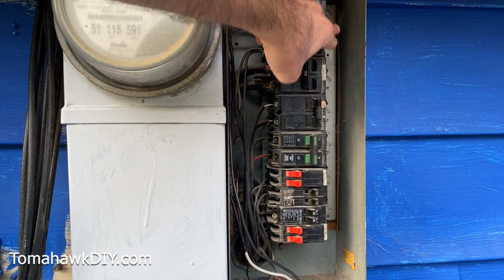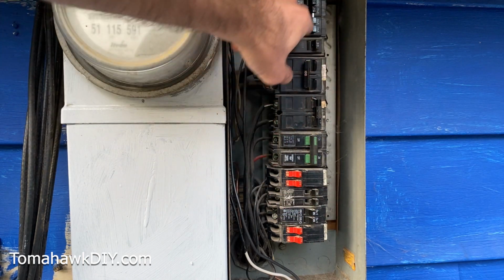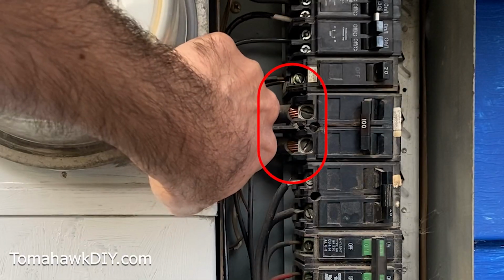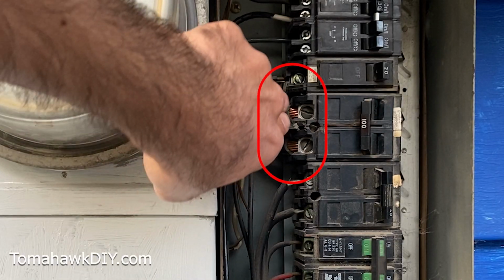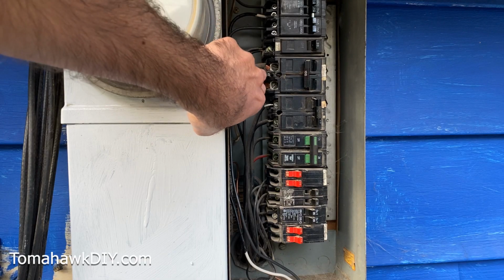The power is dead all at the back here on the bars. It's dead at each of these breakers except the two incoming power feeds right here, so those still have 120 volts. You got to be really careful with that.